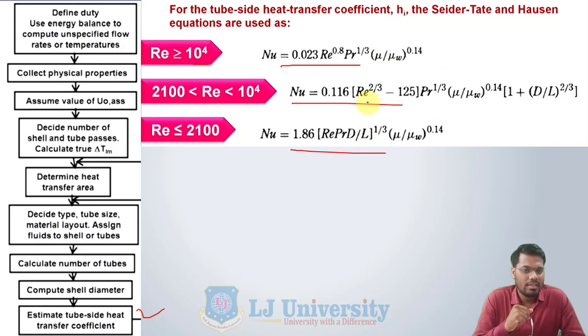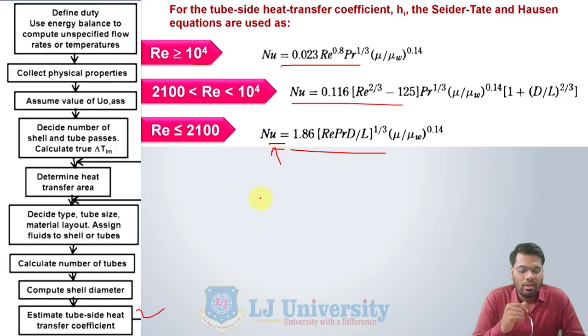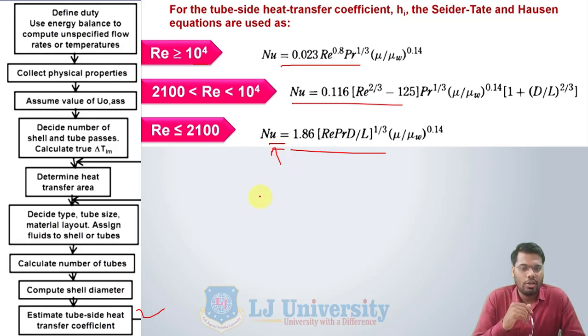By using these relations, we can find out the value of Nusselt. The Nusselt number is equal to h·Lc divided by k, where Lc is the characteristic length — for tubes, it is the diameter. So after getting the value of Nusselt, we can easily calculate the value of h, which is our heat transfer coefficient for the tube side.